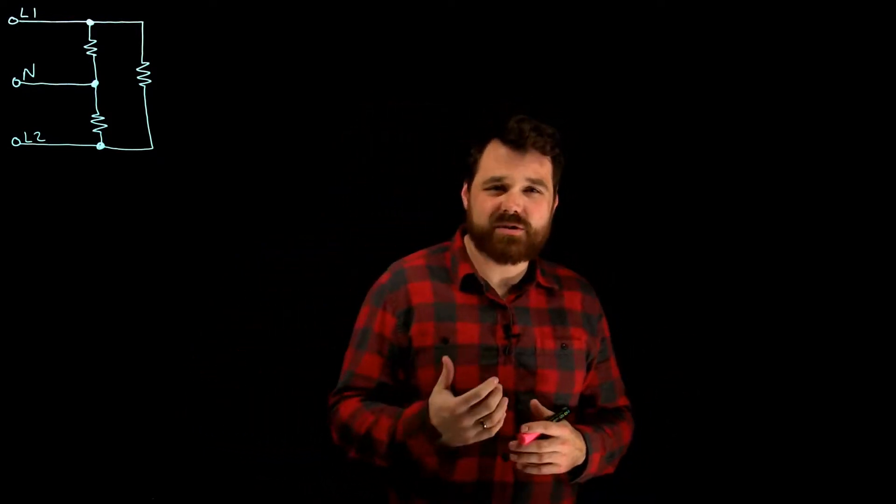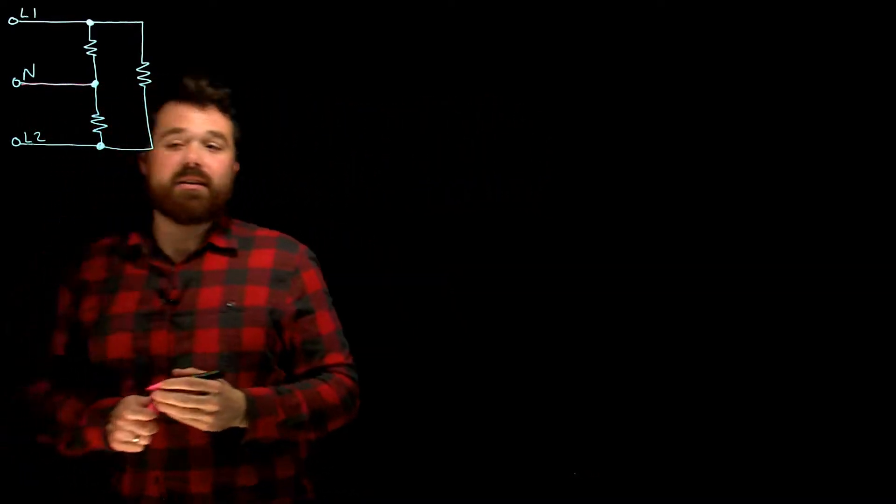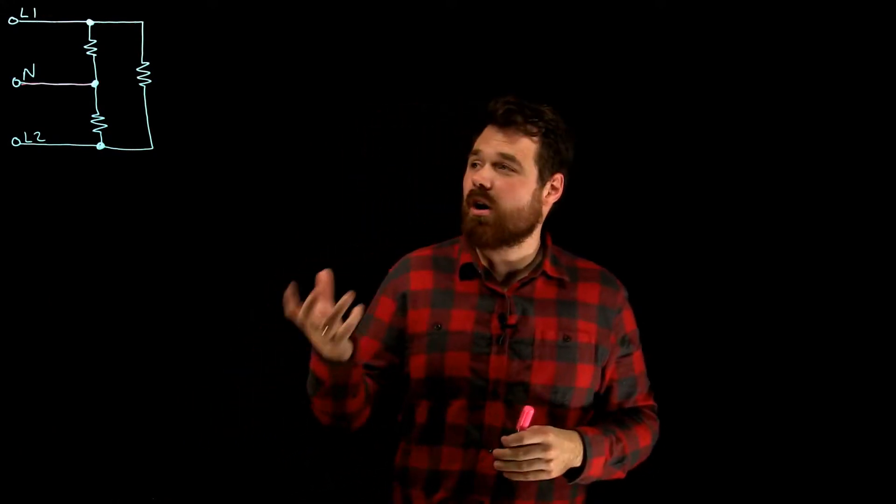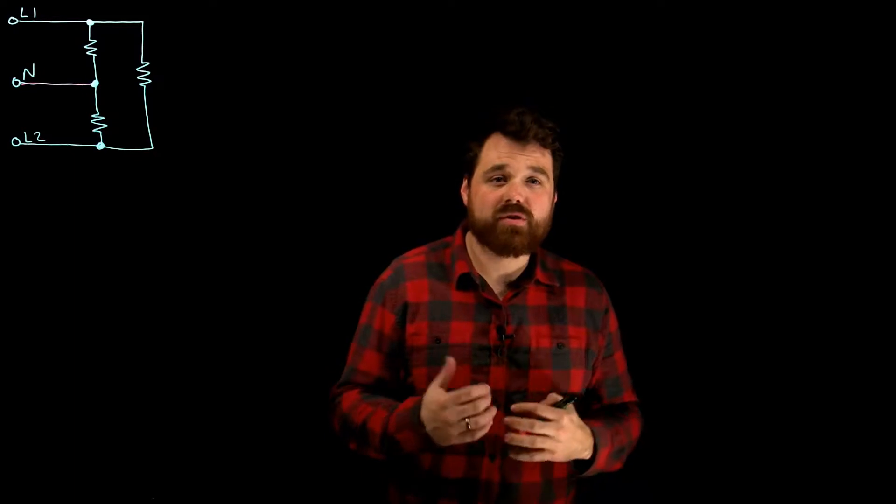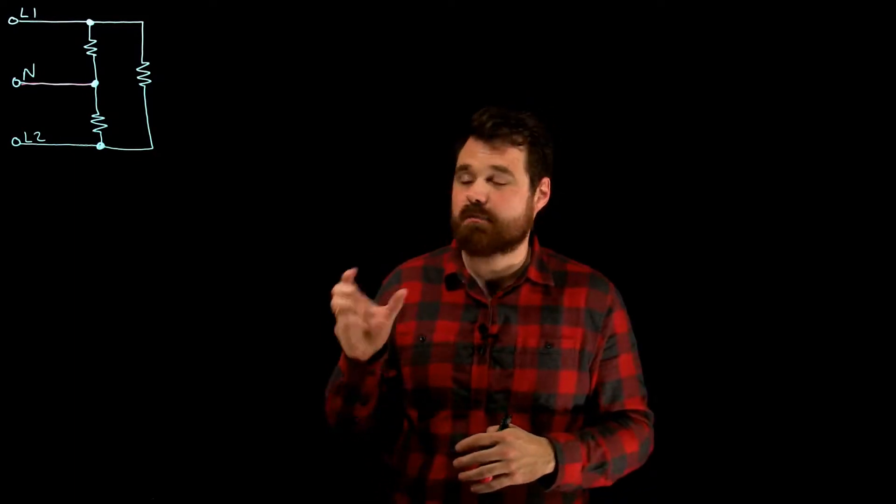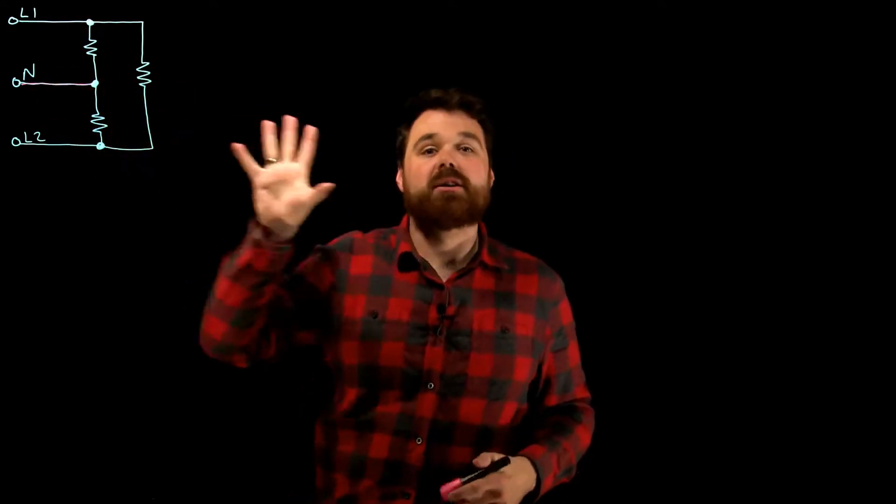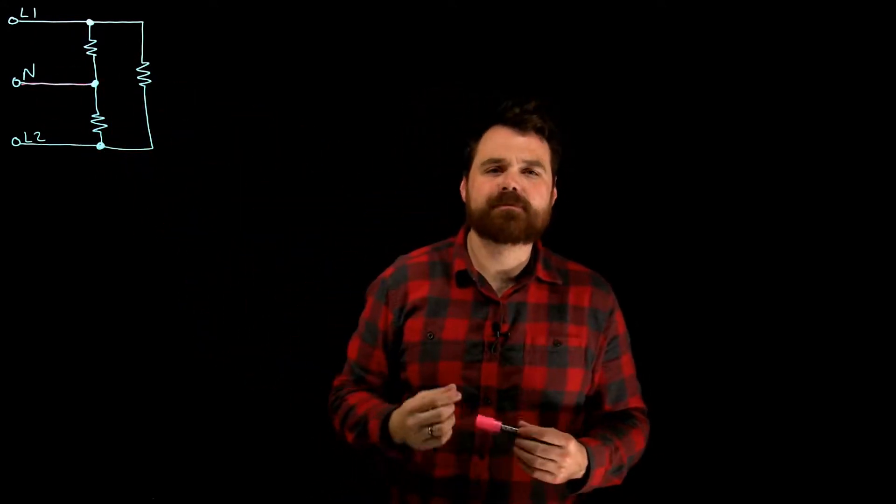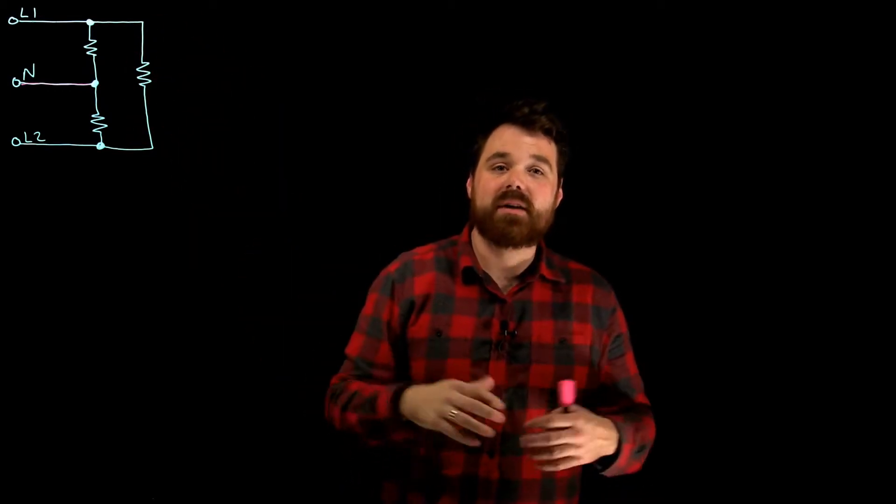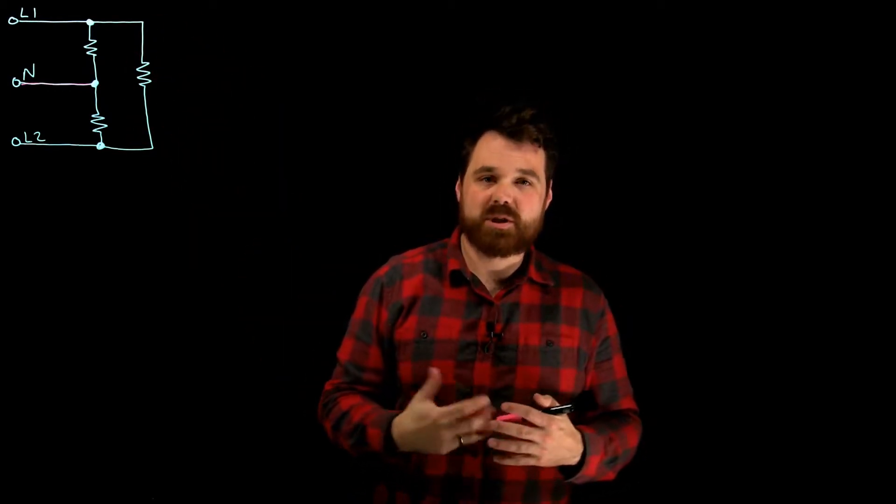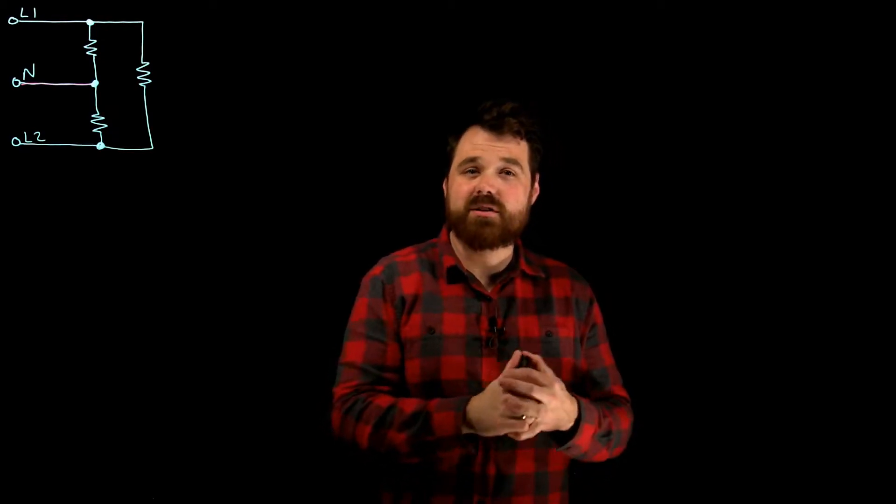So the Canadian Electrical Code allows us to actually reduce the size of that conductor because it's not always going to be seeing that full ampacity or the full load. The code book tells us that it has to be big enough to carry the unbalanced load, meaning I would have to do the calculation and make sure that I can carry the unbalanced load. But a lot of times because we have so many line-to-line loads, that unbalanced load is going to be a little bit smaller. So if that's the case, the code book is going to allow us to reduce the neutral size.